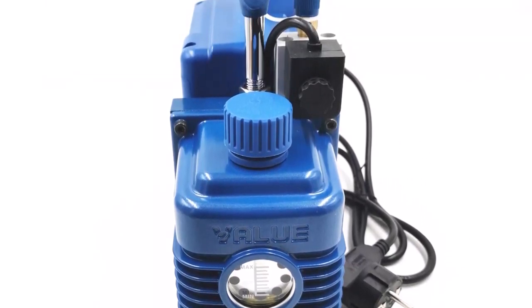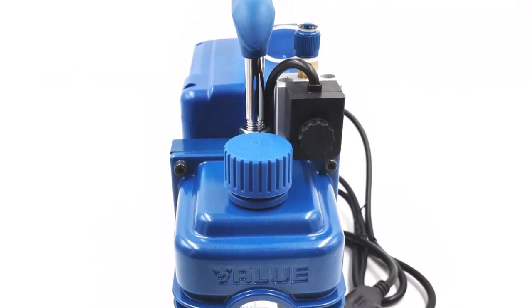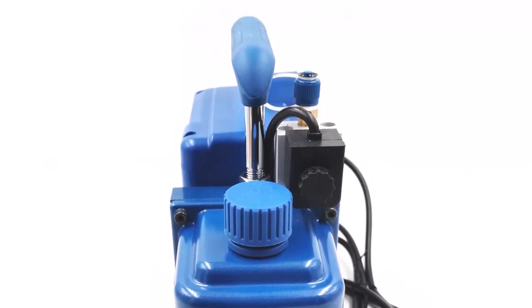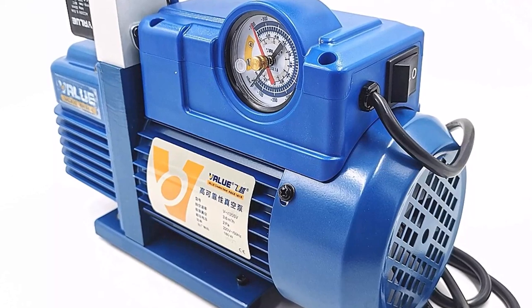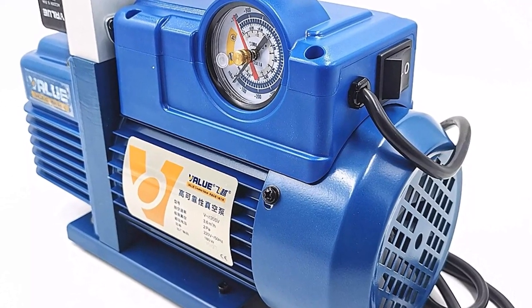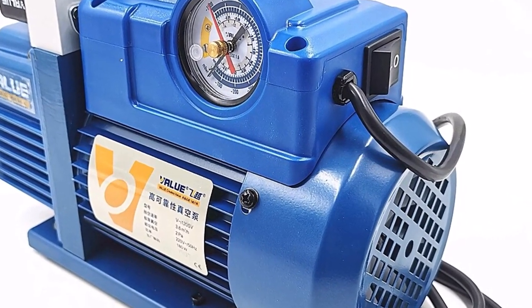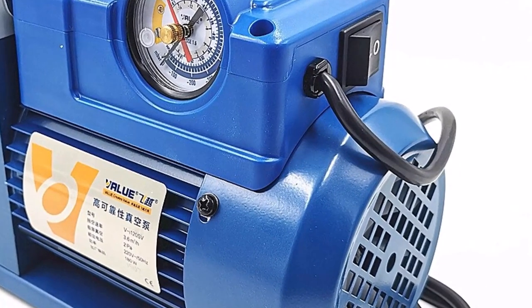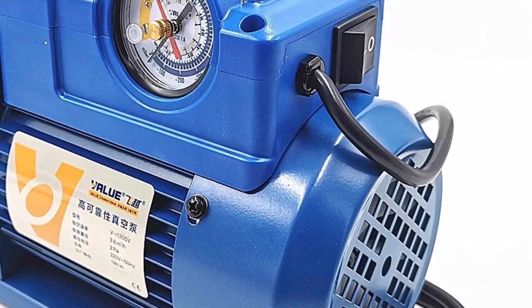High accuracy vacuum gauge shows system pressure. Automatic anti-backflow valve design. Large sight glass for monitoring oil level. Product number VI120SV; rated voltage 220V/50Hz; pumping rate 3.6 cubic meters/H; ultimate pressure 2 Pascals; motor power 180W; oil capacity 250 milliliters; air inlet connection threads 7/16-inch-20UNF.